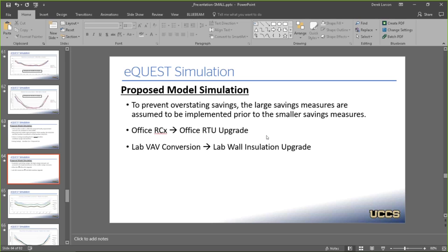So in this case, at the office, we know that RCX is probably going to happen. I mean, we had already talked to them about it, and it's a relatively low cost, high savings item. So that makes sense. And then on the VAV conversion, that's kind of the big saver there. And we also knew that was a higher priority for them than the wall insulation. That makes sense. So curiously, do you know how much difference in the VAV conversion sizing the wall insulation would affect? How much it would reduce that load?